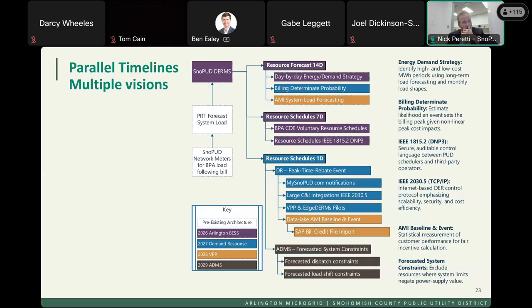No. At our point of common coupling, which is inside a pretty traditional switchgear, we have the same substation equipment we use for our distribution circuits, basically the same spec. The only thing that changed at our point of interconnection was the metering range, because we needed better resolution, and our balancing authority needed better resolution too. We had to add higher capability CTs, which was a pain, about a $100,000 deviation in cost for the switchgear.